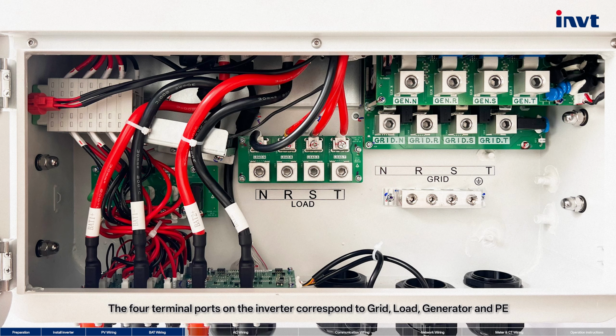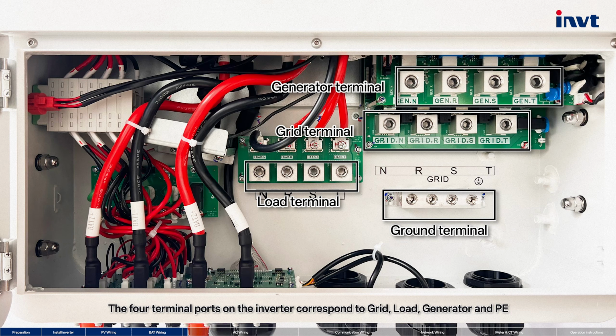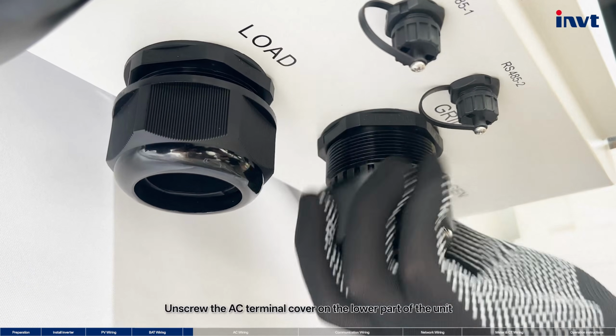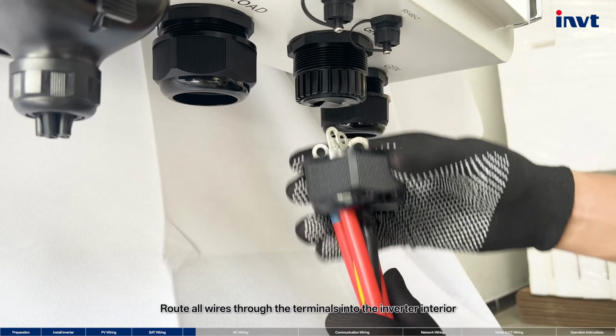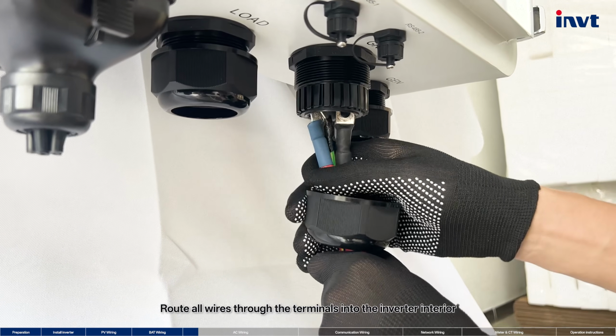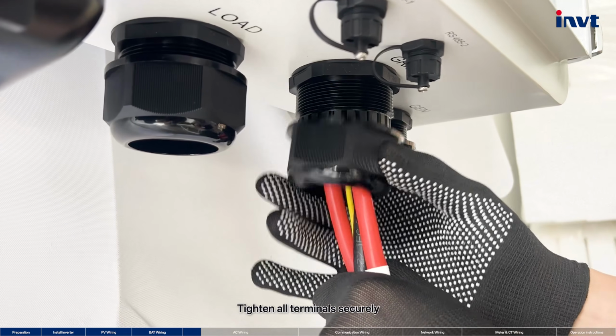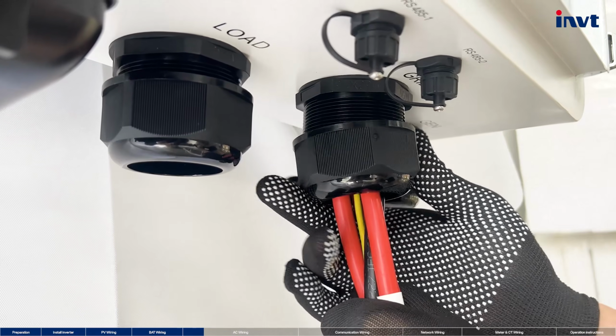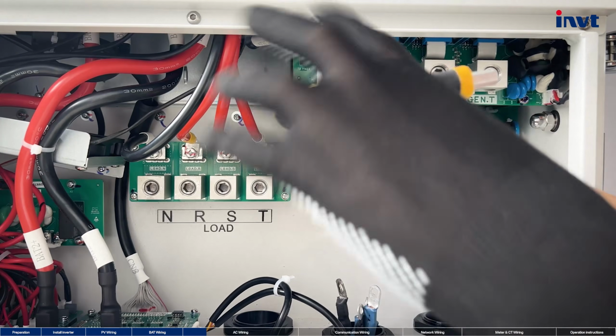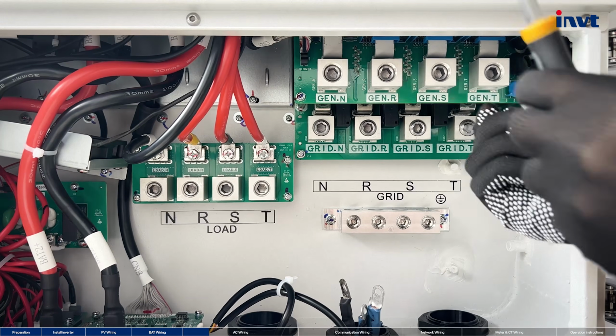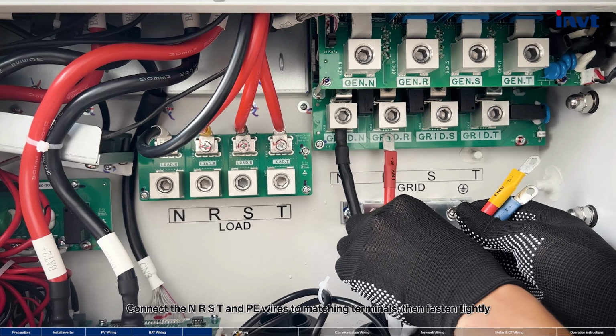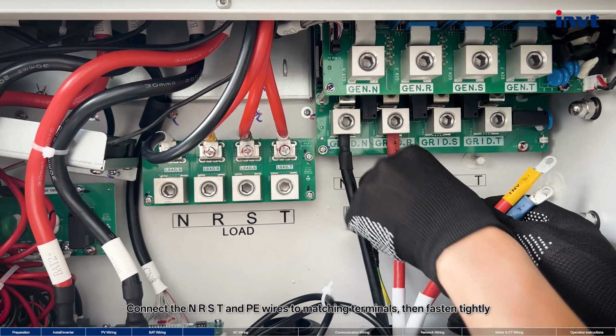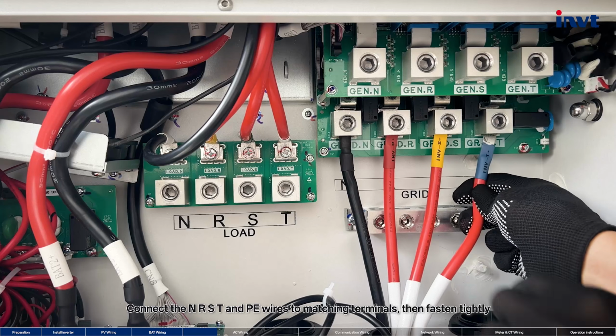The 4 terminal ports on the inverter correspond to grid, load, generator, and PE. Unscrew the AC terminal cover on the lower part of the unit. Route all wires through the terminals into the inverter interior. Tighten all terminals securely. Loosen screws of grid terminals. Connect the N R S T and PE wires to matching terminals, then fasten tightly.